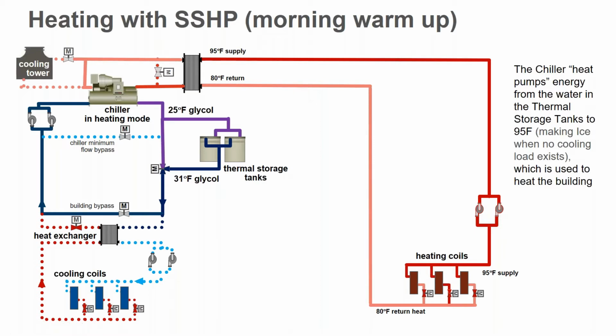I'm showing a centrifugal chiller here with 95-degree supply water going to those coils. I'm being told that can be done now. I think it's terrific. It's an extremely efficient process. If you needed higher temperatures, you may use a screw or a scroll or something of that nature. But the point is, you've got a lot of energy in the tanks when they are full of water, and we're going to take that energy and pump it up to a usable level.